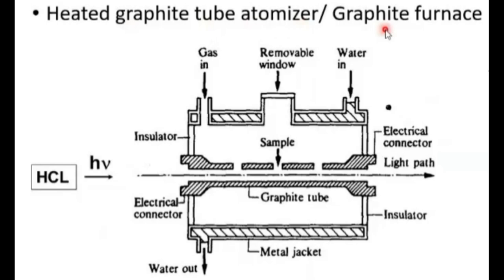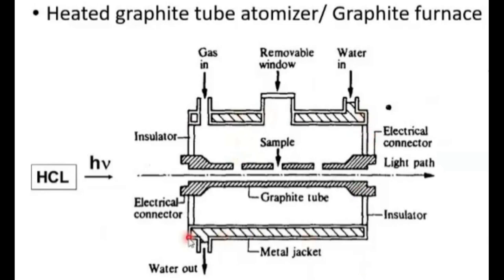Let's look at the heated graphite tube atomizer — simply called the graphite furnace. The graphite tube has one opening for sample introduction. Gas enters and exits the graphite tube. The gas also surrounds the tube from both sides, and this neutral inert gas flows continuously.